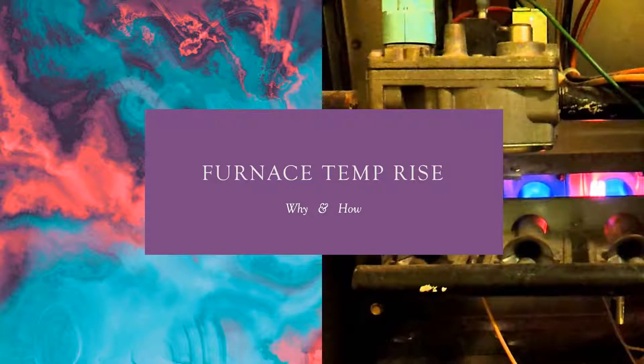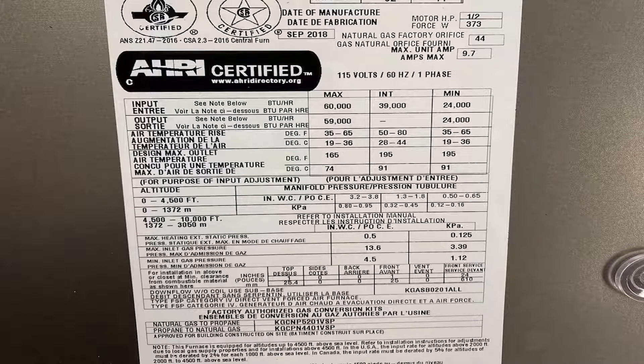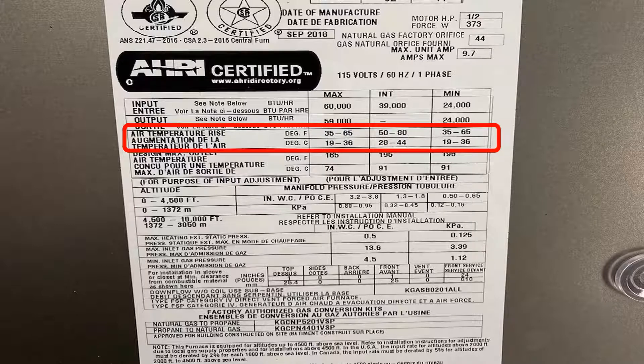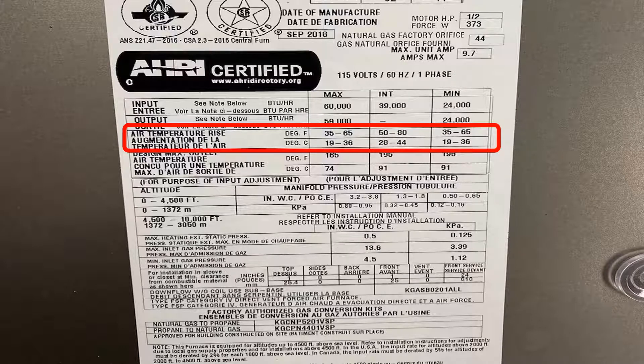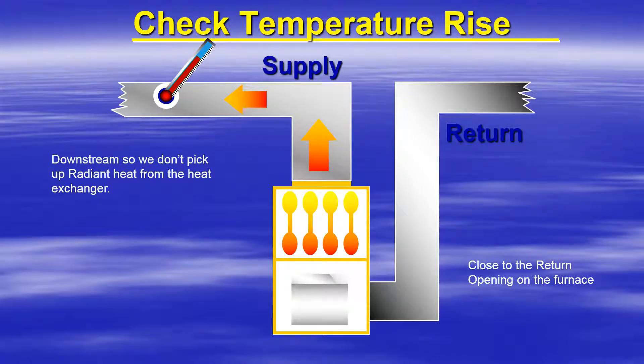Furnace temperature rise — why and how. On all furnace data tags you will find a section with the air temperature rise parameters. In this particular example, this is a modulating furnace, so we have an air temperature rise parameter for maximum, intermediate, and minimum furnace operation. The temperature rise should be taken for all three, as all three have different gas pressure settings.